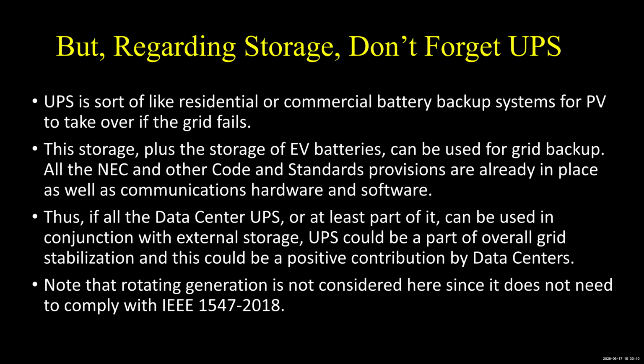IEEE 1547-2018 says you can sell electricity back to the utility at the utility's request, when the utility's frequency begins to drop, meaning it's becoming overloaded. Rather than shutting down or getting out of the way and making things worse, you can keep your solar or wind running and be part of the solution. We're not talking about downed transmission or distribution lines causing a total outage, just an overload on the system. How do we fix it? If we can fix it locally with batteries, maybe we avoid a blackout or brownout.